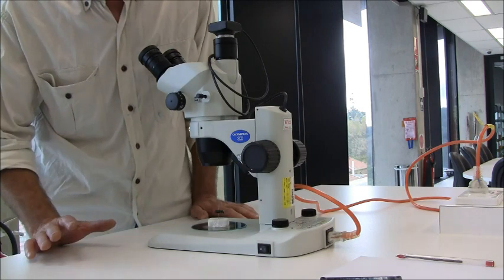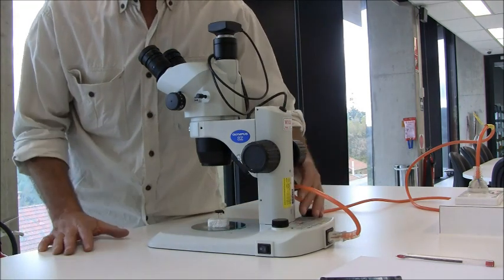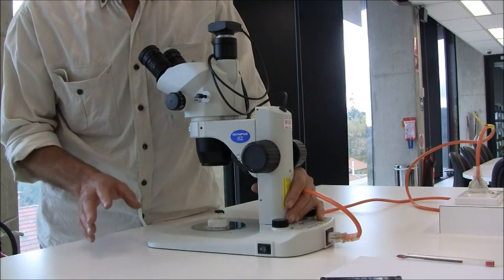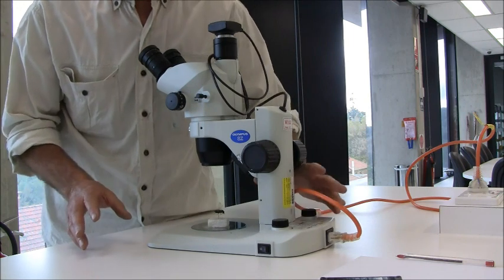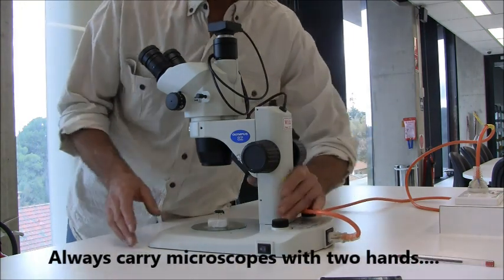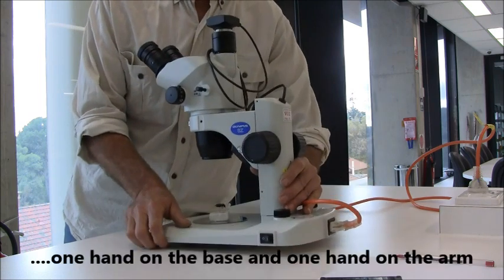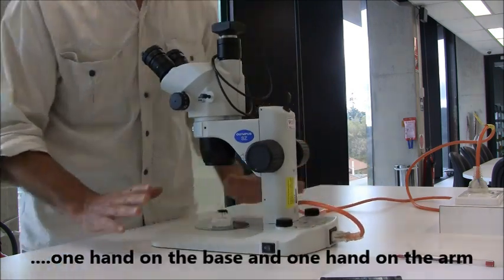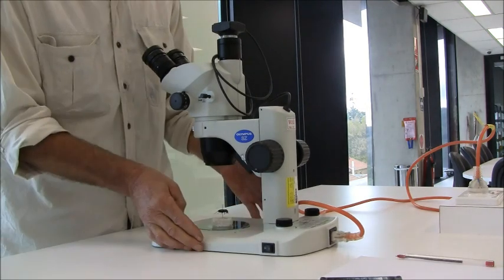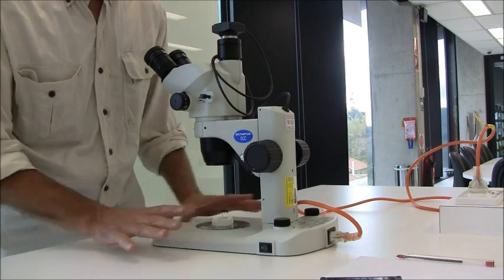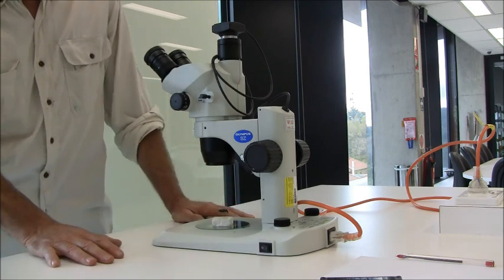Now, setting this microscope up, I'll first mention how to carry them. They're quite expensive, and if you drop them they certainly won't come out well. Grab it by the post and by the base with a nice firm grip. Once it's on the bench, set it up where it's convenient and then leave it there. Pushing it around the bench is not good either.